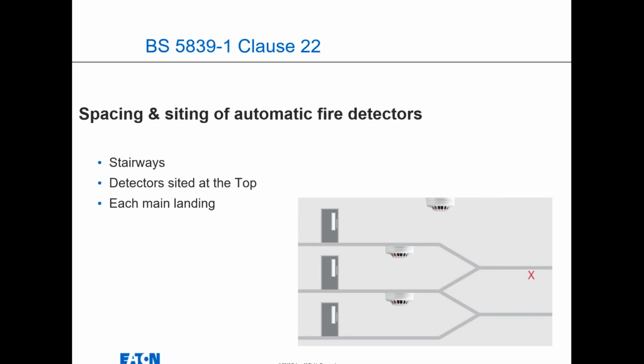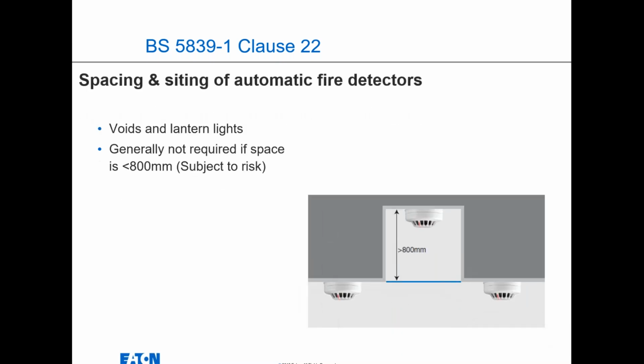So stairways, detectors, again you need one at the top of the stairwell, and then one in each main landing. So not sub landings, just main landings. Voids and lantern lights are generally not required if the space is less than 800 mil. So if you've got less than 800, you don't have to have a detector within that space.